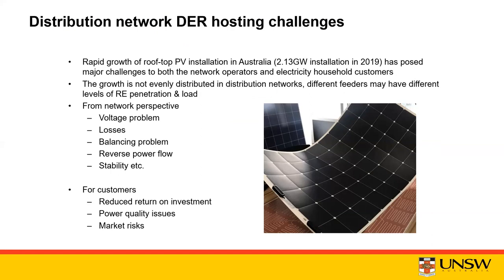So the rapid growth of PV installation causes major challenges. One of the challenges is the imbalanced network. As we know, in the growth of a distribution network, some households connect on one phase, some on another. For a three-phase feeder, the installation or growth of rooftop PV is not even, and also the demand is not even. Conventionally, this is handled by switching, by resetting the different phases, and by tuning tap-changing transformers. But with rapid growth, this is no longer sufficient.